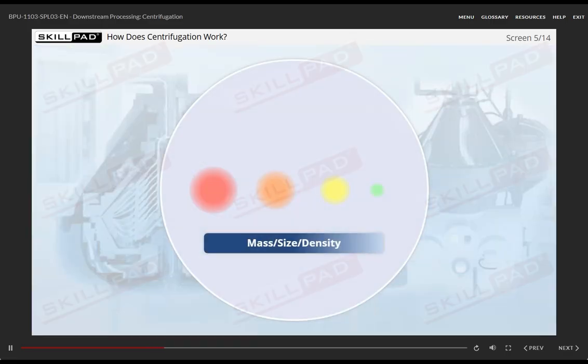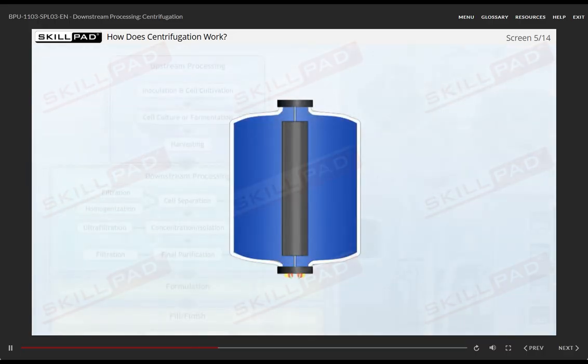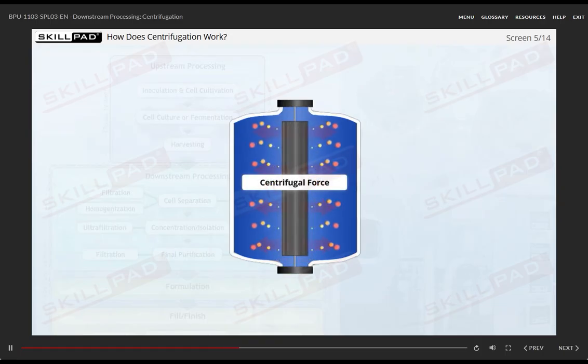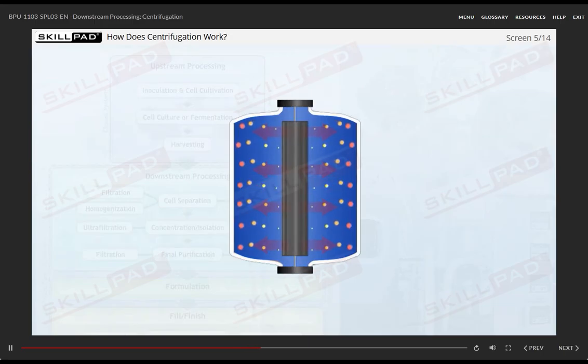To understand how this works, let's consider a mixture of particles in solution containing particles that differ in mass, size, density, and so on. As the centrifuge rotates, it causes the components of the mixture to experience an outward force away from the center of rotation. The heavier the particle, the further away from the center it will move. The speed of the rotor is measured in revolutions per minute, or RPM. The greater the RPM, the greater the centrifugal force.